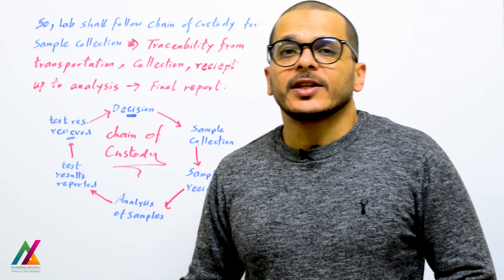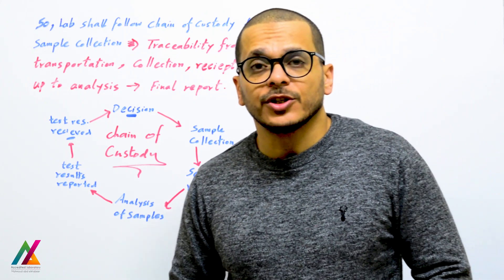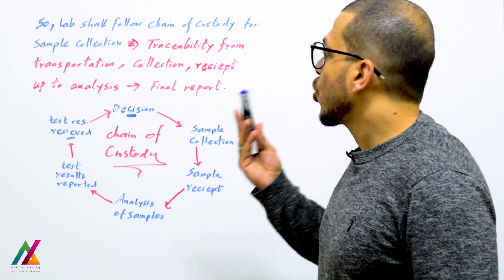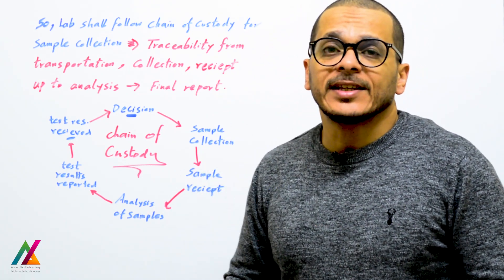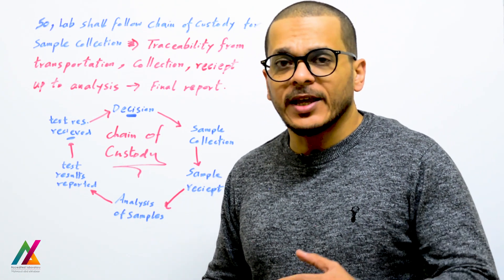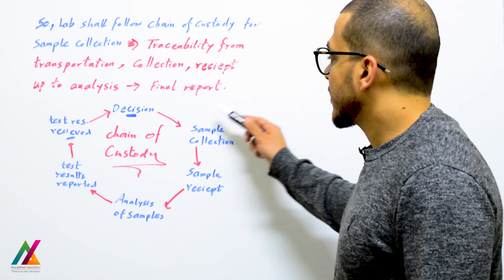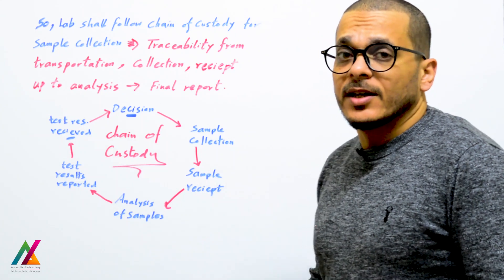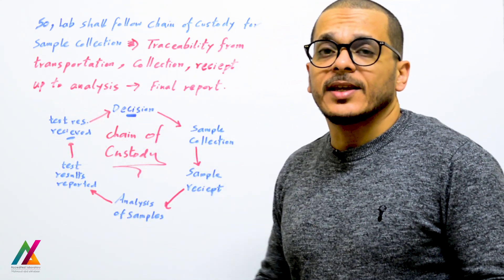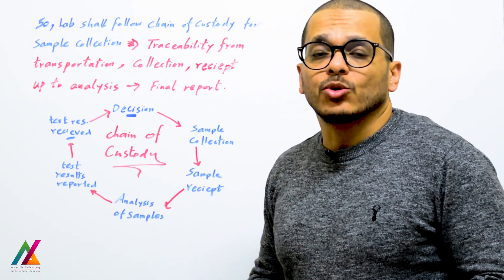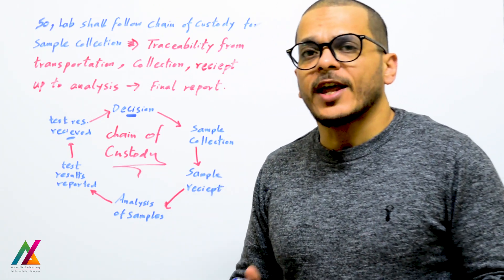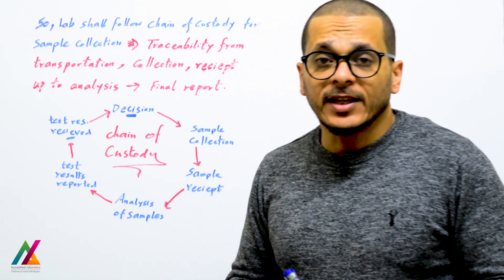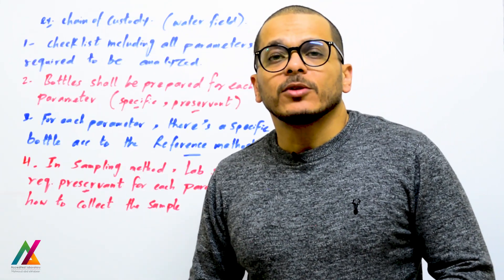In the case of sample collection, the lab shall follow chain of custody as explained in the previous lecture on sampling (clause 7.3). Chain of custody means traceability of the sample from collection and transportation through receipt, analysis, and the final report — to keep the integrity of the sample and the integrity of the results. This supports decision makers who use the reported results to accept or reject a sample.